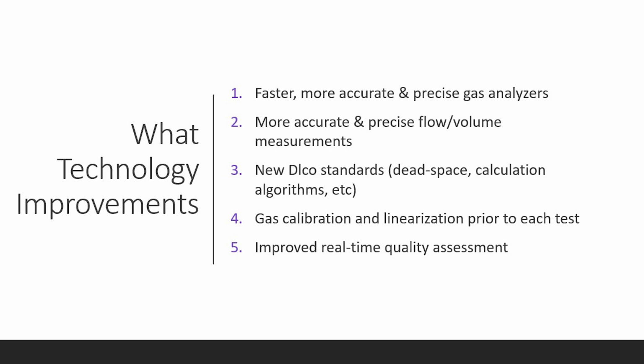Faster, more accurate, precise gas analyzers. And this is all technical stuff that technical people and engineers deal with, but they actually worry very, very seriously about reducing the variability and increasing the accuracy of the internal components of these devices. The same goes for the more accurate and precise flow volume measurements. And the new DLCO standards have now demanded new ways of calculating dead space, where you start calculations from, and algorithms and so forth and so forth.